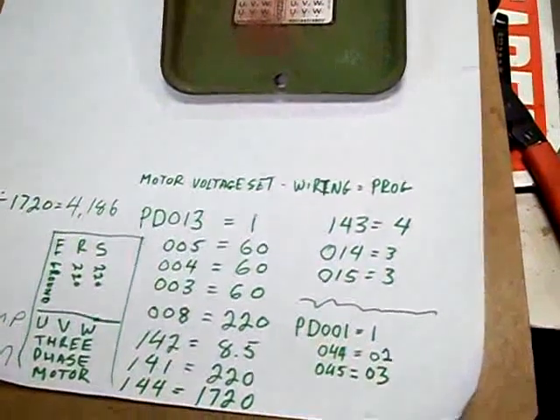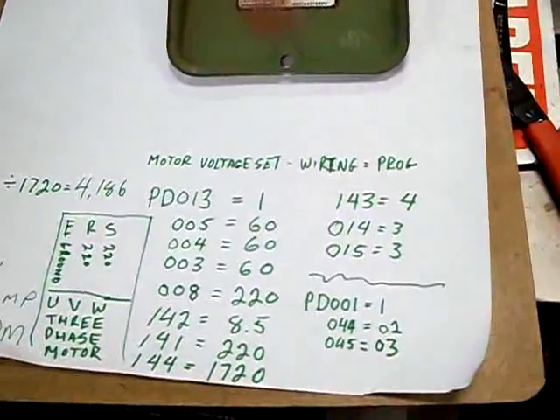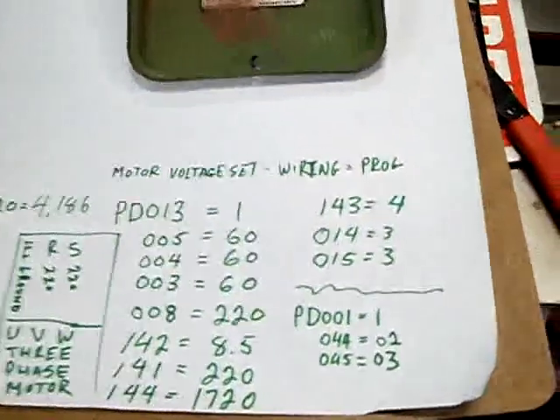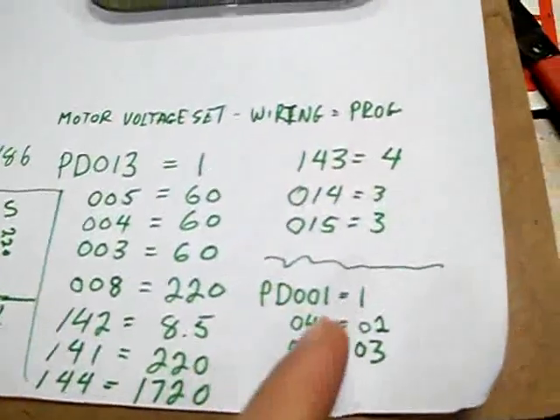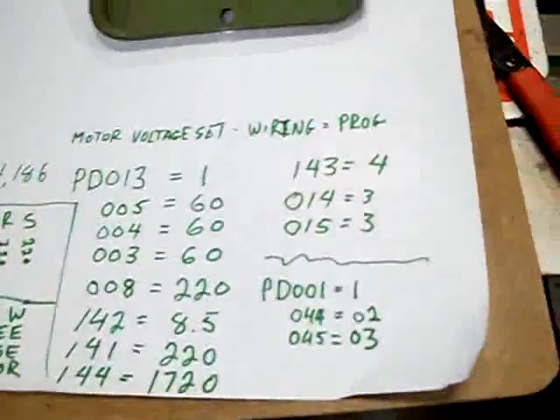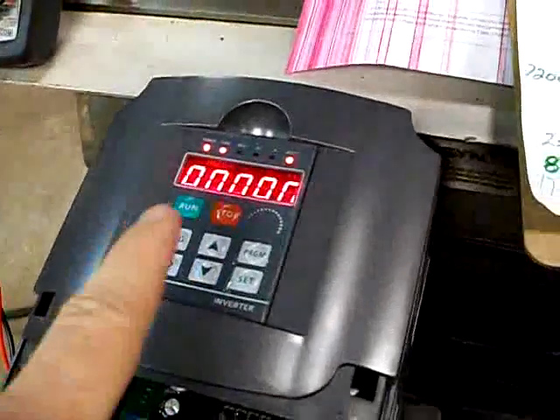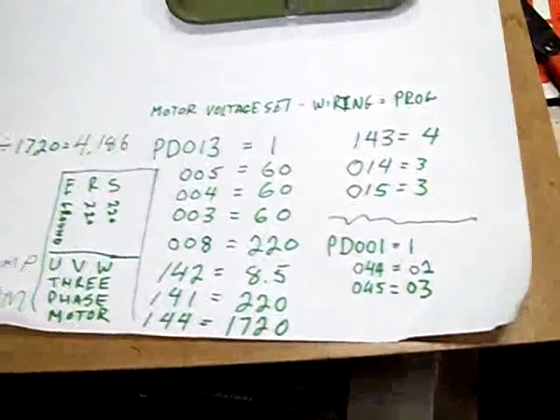And then these parameters here are set up for forward and reverse switch. So you just set up the 001. Once you set up that 001, you won't be able to hit run anymore to start the motor up. You're going to need to use a switch.